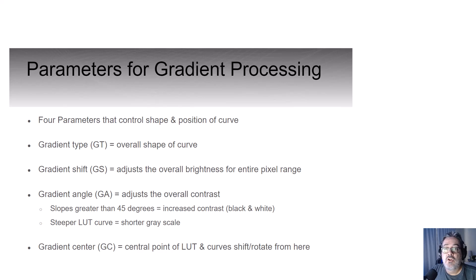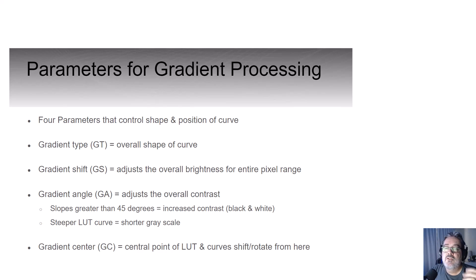There are four parameters that determine the shape and position of the curve in gradient processing. Gradient type is the overall shape. Gradient shift adjusts the overall brightness for the entire pixel range — brightness is controlled by left to right changes in the curve. Gradient angle adjusts the overall contrast; contrast is influenced by the steepness of the curve, and slopes greater than 45 degrees have increased contrast or very black and white images. A steeper lookup table curve means a shorter grayscale and higher contrast. Gradient center is the central point of the lookup table, and curves shift and rotate from that point.